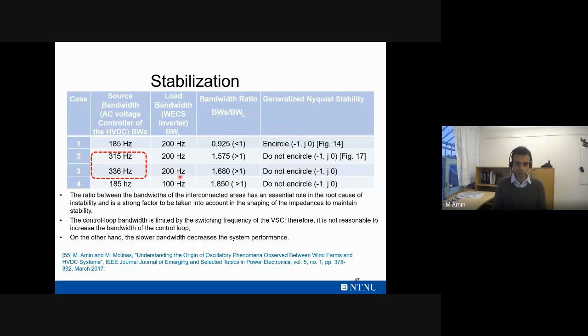The other way is to decrease the bandwidth of the wind energy conversion system, which also stabilizes it. This control bandwidth depends on the switching frequency - we try to keep the outer loop 3 to 10 times slower than the inner loop, and the bandwidth is limited by the switching frequency, the inner and outer loops, and the PLL. So it's not always possible to change the bandwidth, but this is one way to stabilize the system.